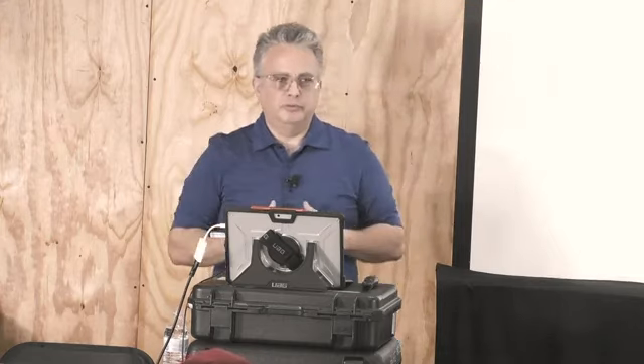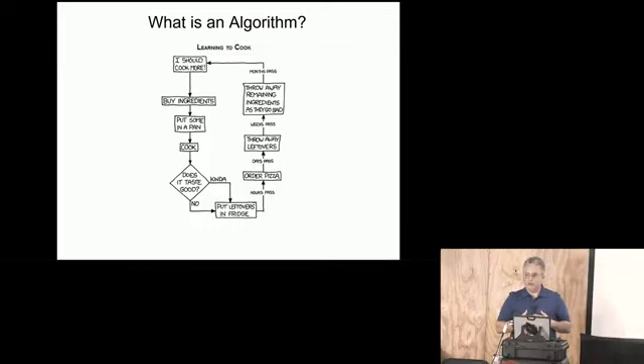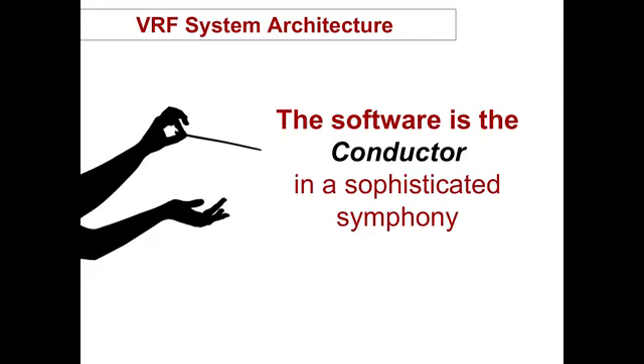Now imagine a typical air conditioning system coated with lint, maybe half an inch thick. What would happen? Something, right? You wouldn't be cooling. But because of the algorithms, the software programming, the discharge temperature is monitored, and the system just lowered the compressor, increased the fan motor to maintain that discharge temperature in its happy spot, right? Which can be somewhere between 160 and 220 degrees, depending. So was that a good understanding of how the software can work? Yeah? Set of instructions.